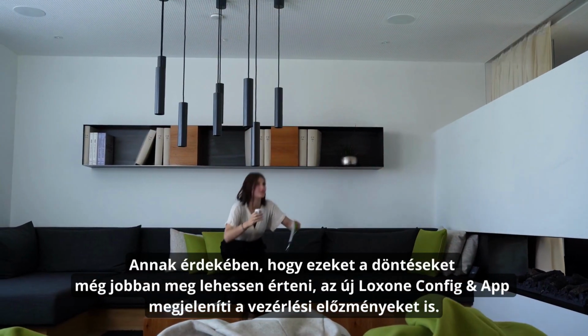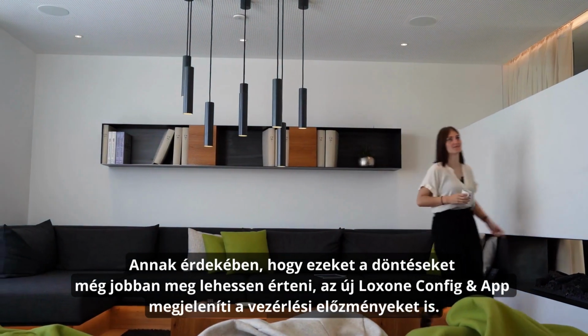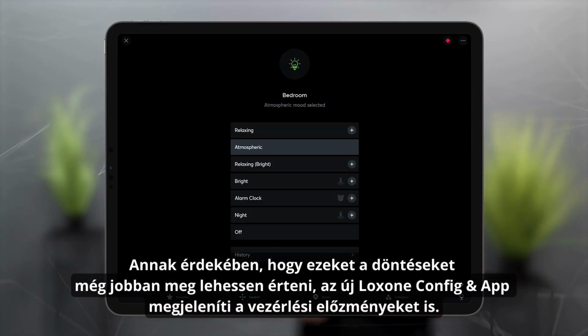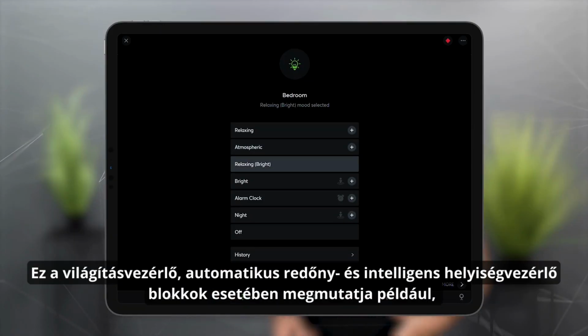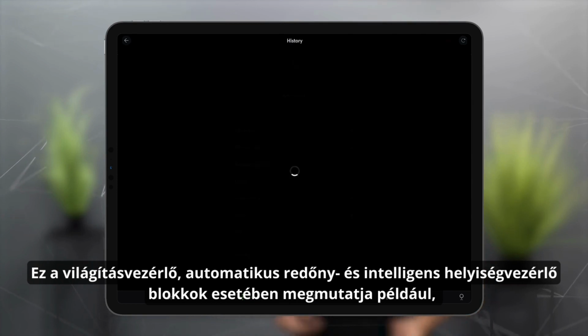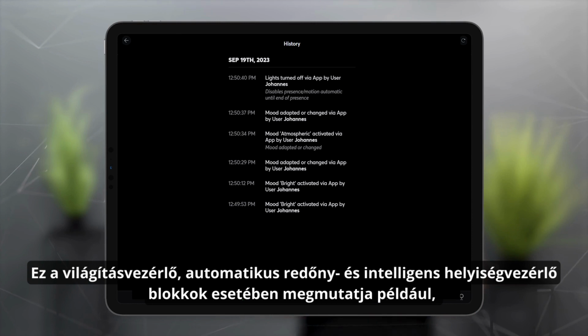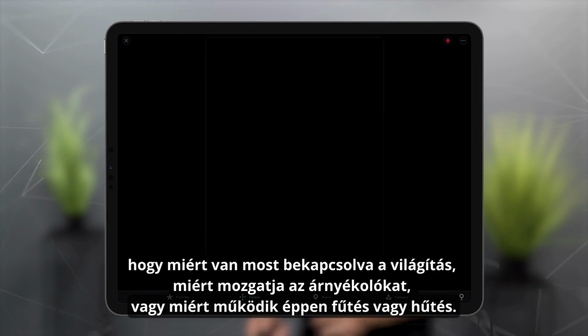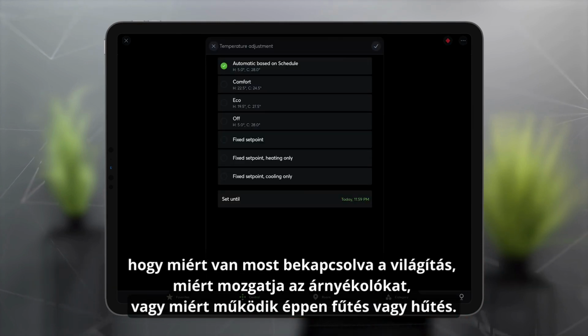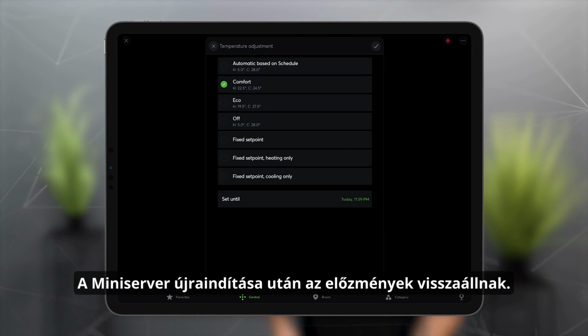In order to be able to understand these decisions even better, there is a new control history with the new Loxone Config app. For our lighting control, automatic blinds and intelligent room controller blocks, this shows why, for example, the lighting is on, why the shading is active or why heating or cooling is currently taking place. After a mini server restart, the history is reset.